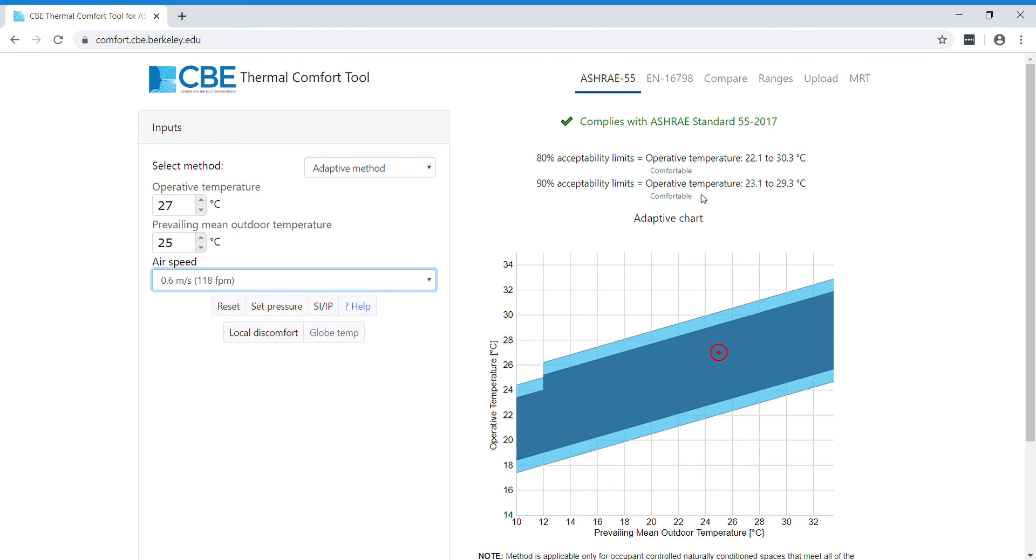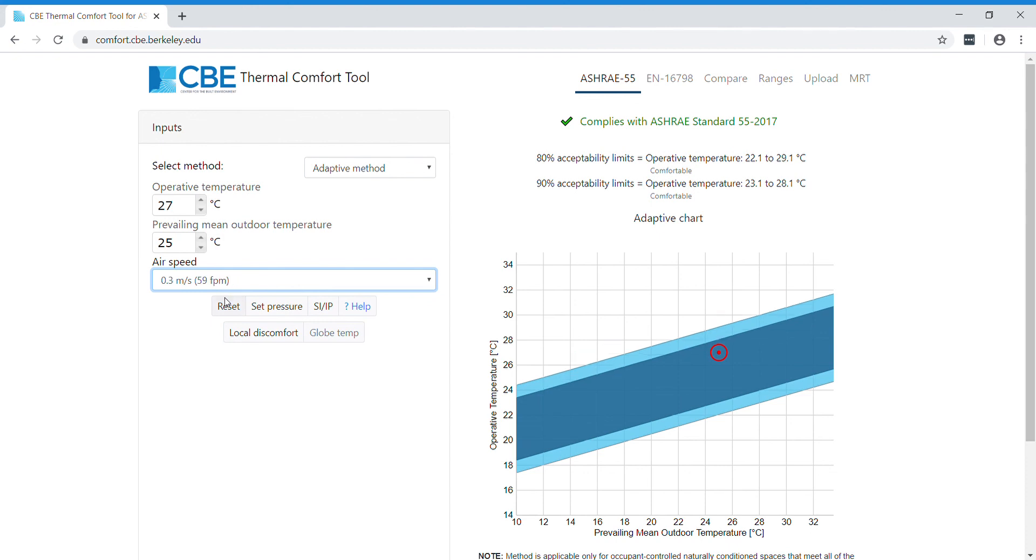If you want to make sure that 80% or 90% of the occupants are comfortable, for this specific prevailing mean outdoor temperature, we can see that 80% of the occupants are comfortable if the temperature is between 22.1 and 29.1 degrees.